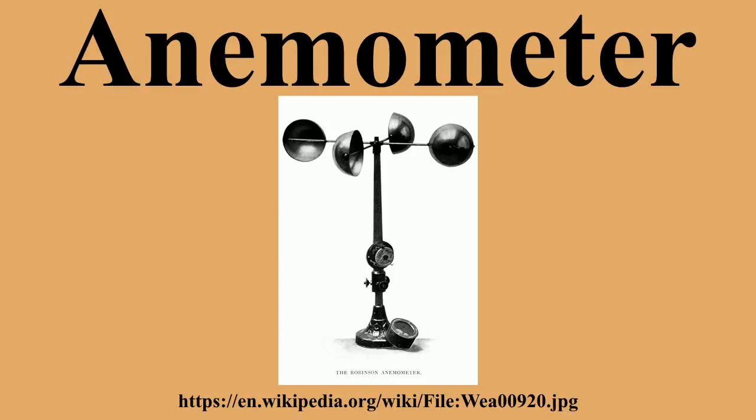Acoustic resonance anemometers. Acoustic resonance anemometers are a more recent variant of sonic anemometer. The technology was invented by Dr. Savas Kapartis and patented by FT Technologies in 2000. Whereas conventional sonic anemometers rely on time-of-flight measurement, acoustic resonance sensors use resonating acoustic waves within a small purpose-built cavity in order to perform the measurement.